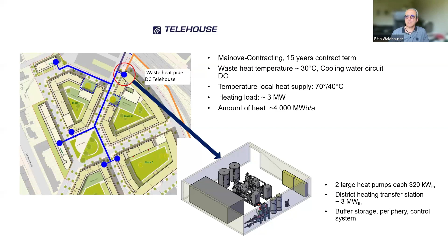They're quite expensive, and therefore Mainova decided to make that compromise and not to install everything, and start with the 2 large heat pumps only. Therefore we come at the end of the day at about 60% of the waste heat from telehouse, and the remainder of max 40% from the district heating system. On the next slide, you can see what are the challenges.